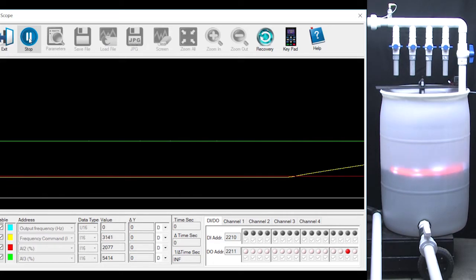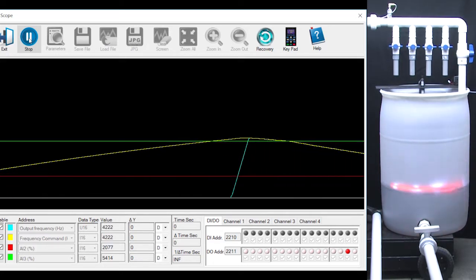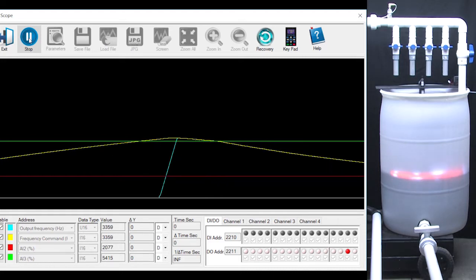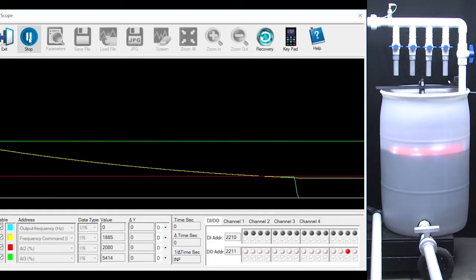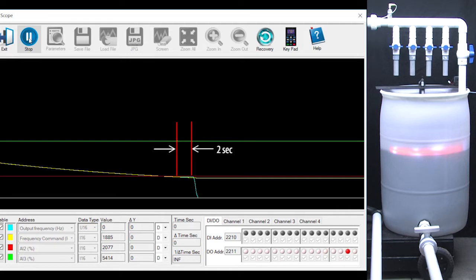Now when we run the test, I'll speed up the video here, we see sleep waits 2 seconds after hitting the wake up level to turn the motor on and it waits 2 seconds after hitting the sleep level to turn the motor off. So the sensor's signal had to be past the threshold and stay there for 2 seconds before sleep would activate. That's a great way to get rid of intermittent threshold crossing due to noise for example.